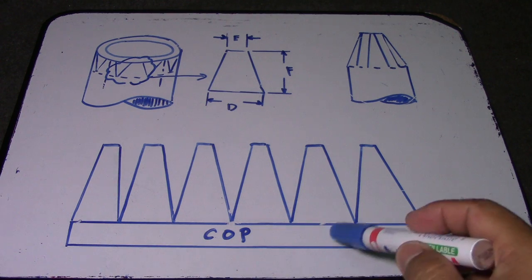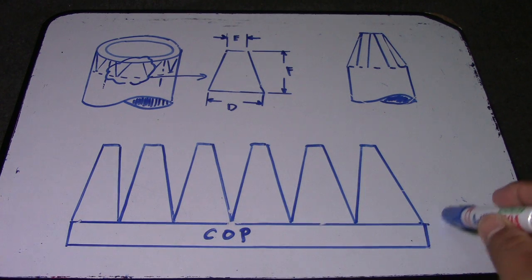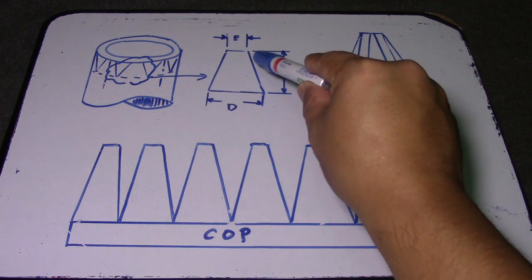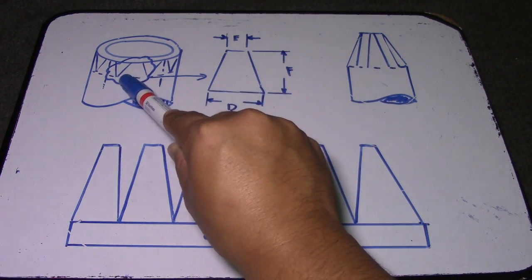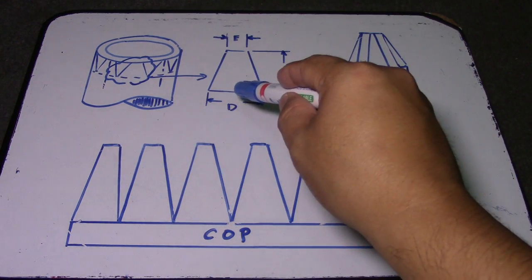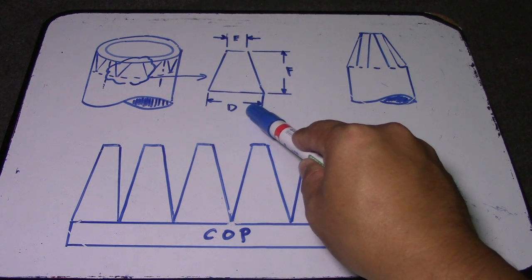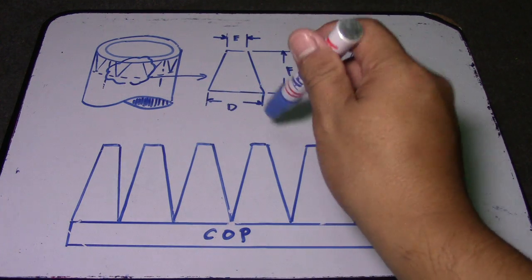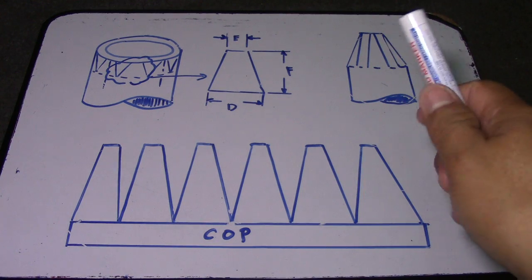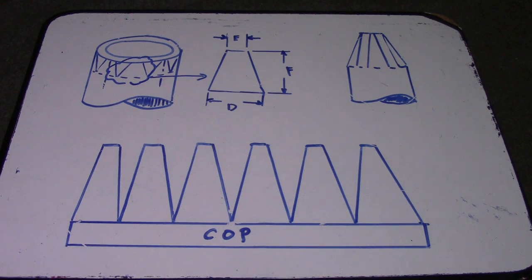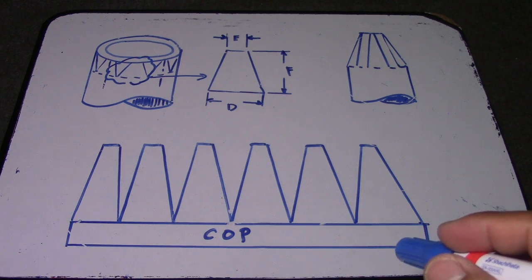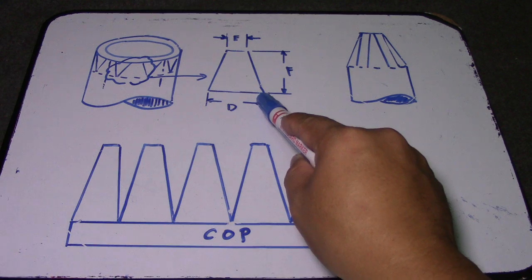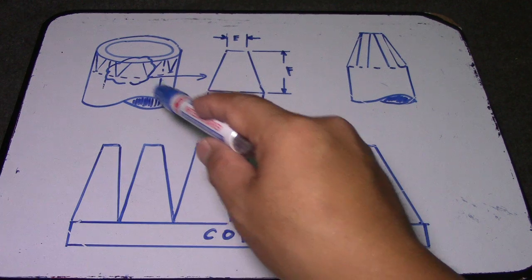We also have a template for the concentric reducer. First, how to compute this triangle from this pipe. To get letter D, take note of this formula: D is the circumference of the large pipe divided by the number of arms. We have a minimum of four arms.